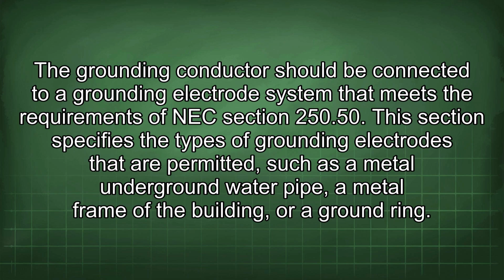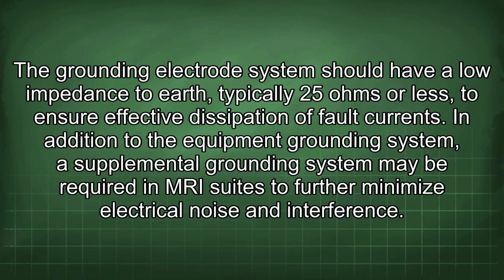Section 250.50. This section specifies the types of grounding electrodes that are permitted, such as a metal underground water pipe, a metal frame of the building, or a ground ring. The grounding electrode system should have a low impedance to earth, typically 25 ohms or less, to ensure effective dissipation of fault currents. In addition to the equipment grounding system, a supplemental grounding system may be required in MRI suites to further minimize electrical noise and interference.